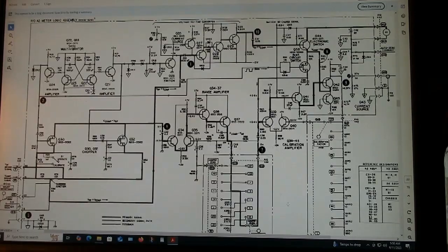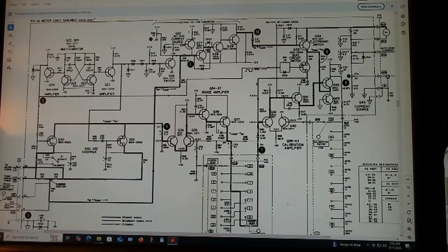And these two signals are going to be applied to the meter logic circuit, which is on another board. Here's a diagram of the meter logic assembly, and on the left side you can see the VRF signal and the V comp signal are applied to this assembly. The function of the meter logic assembly is to take the two signals from the bridge assembly and to produce a V comp minus VRF and a V comp plus VRF, and they do that by applying the signals first to this chopper here that's driven by a 5 kilohertz multivibrator.